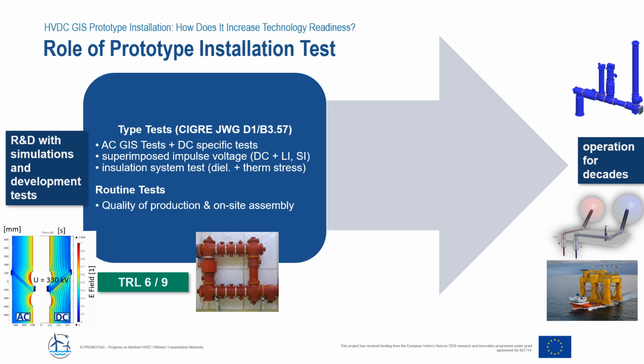However, there are a lot of pre-standardization activities going on, and there are recommendations on testing, for example, from CIGRE, that recommend to include an insulation system test that combines dielectric and thermal stresses, that includes superimposed impulse voltage, and of course, that includes all the other AC GIS tests like temperature rise or short time withstand current. Because HVDC GIS is a new technology, even a completion of all these type tests would only put the technology readiness level of 6 out of 9, because as of yet we only have very limited operational experience with HVDC GIS.